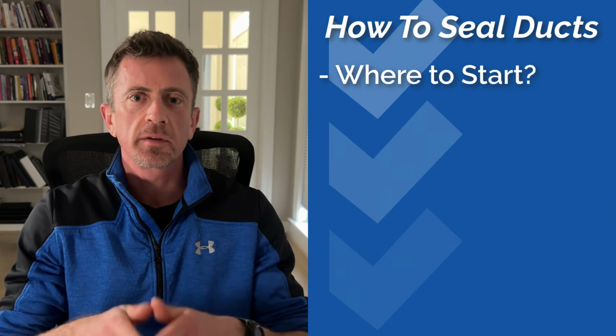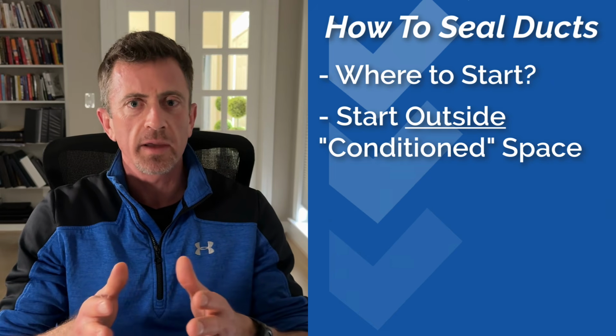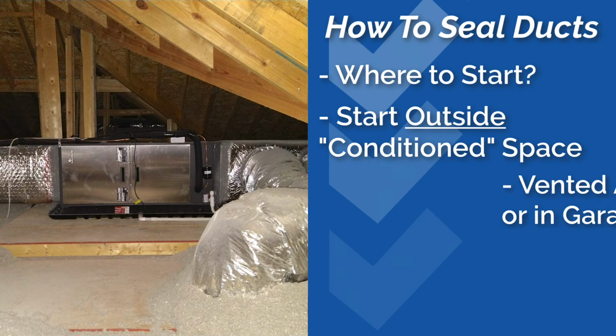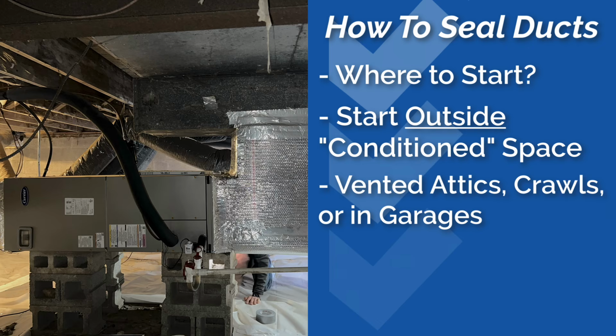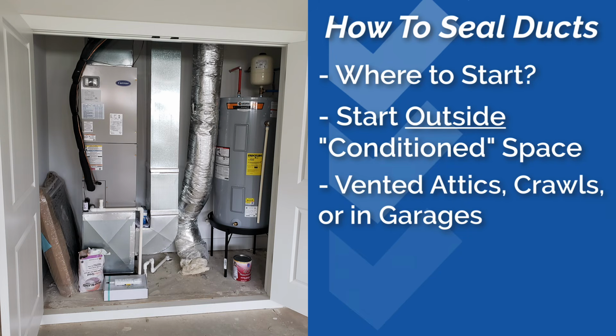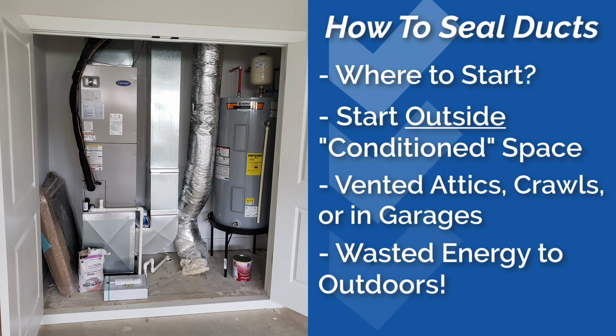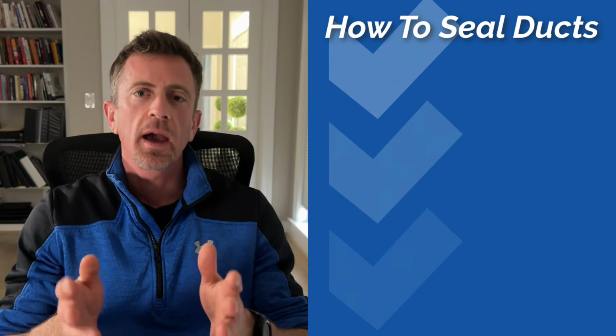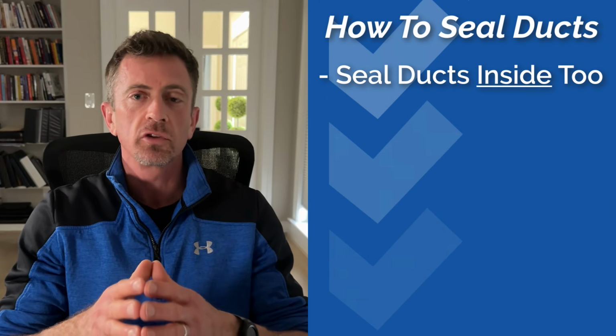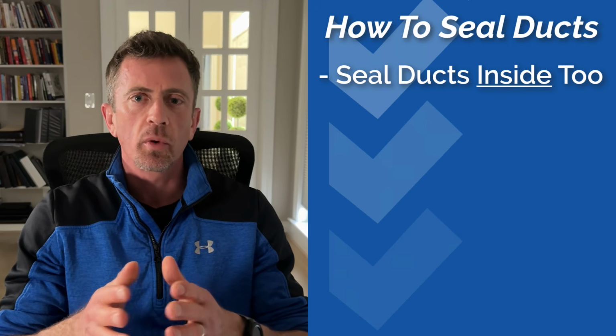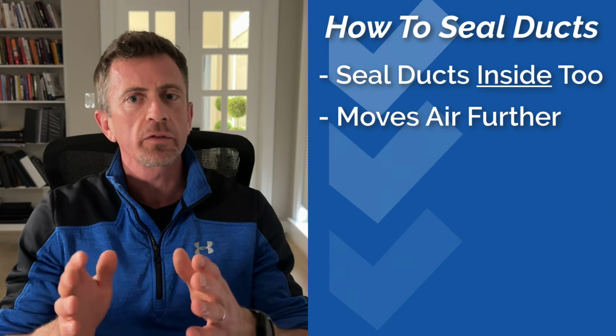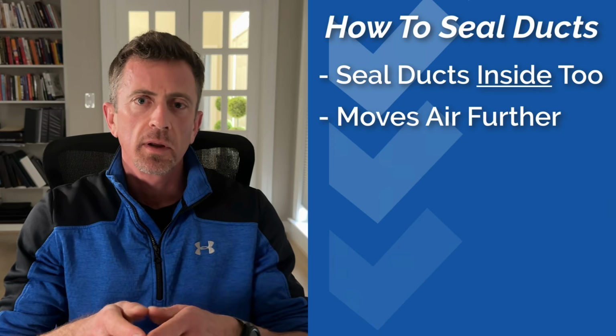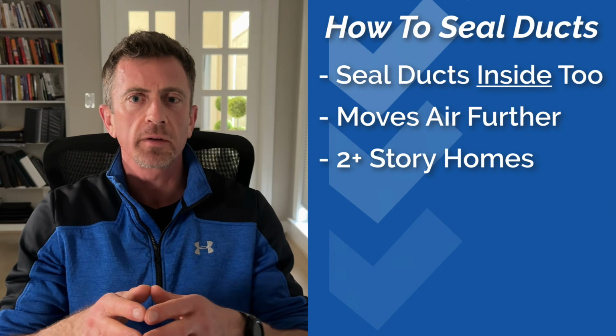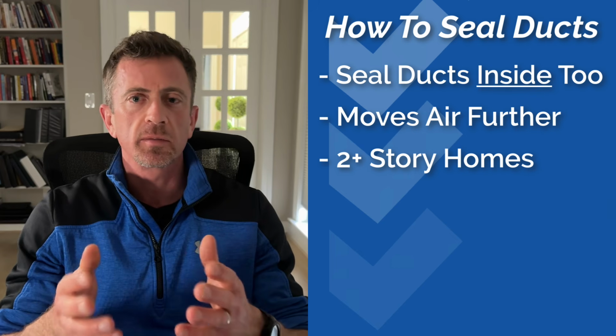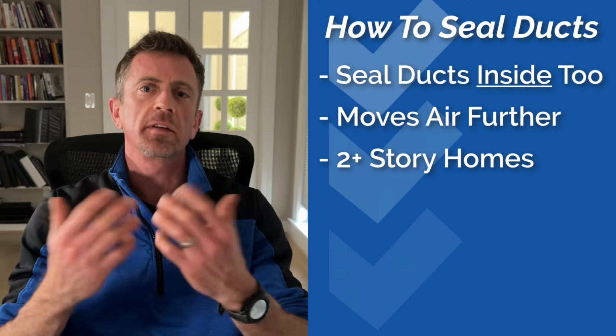So first things first, sealing ductwork located outside the conditioned space is most important. This means any ductwork in ventilated attics, ventilated crawl spaces, or garages needs done first. Since that air isn't staying inside the living space of the house, any leaks there are a direct waste of energy. However, ductwork located inside living spaces should also be sealed. This is especially important to deliver the airflow needed to all the rooms furthest away from the HVAC equipment. This is a really common problem in 2-story houses or more, where the HVAC system is located in the basement and it's trying to send air to the top.